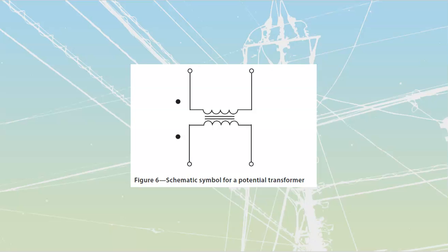Our next type of transformer is the PT, also commonly known as a VT, or voltage type transformer. They have many turns on the high voltage side, which we're always stepping down to a value in our province of 120 volts. We don't have to carry a lot of power through them, only a little bit, so their VA ratings are going to be 100 VA to maybe 500-ish VA.